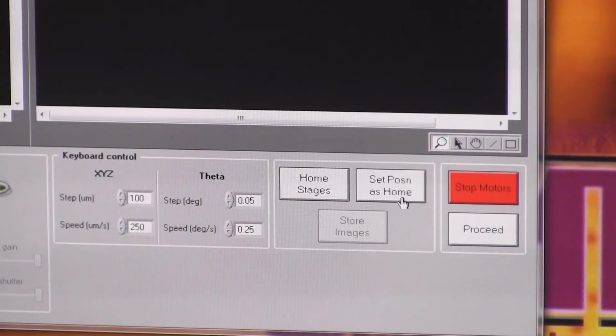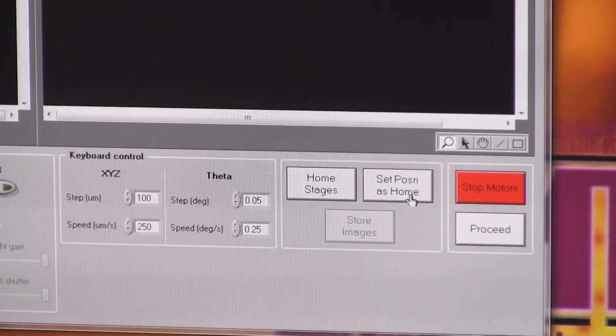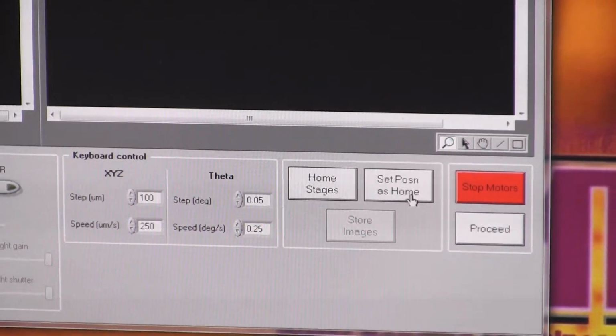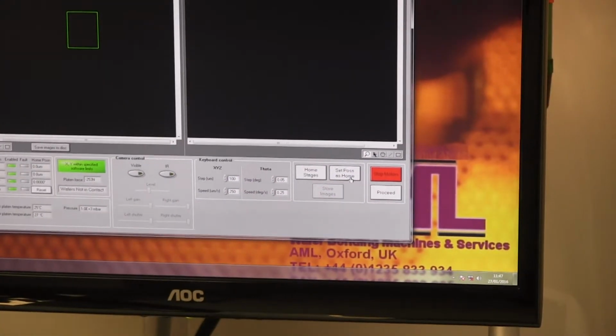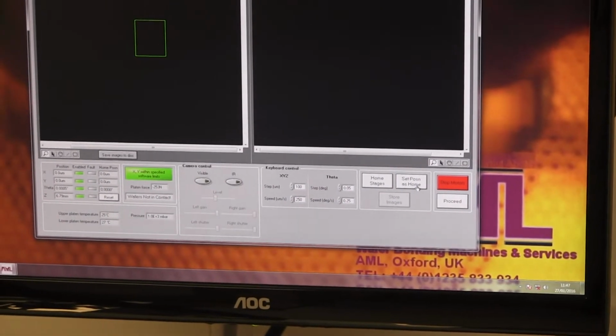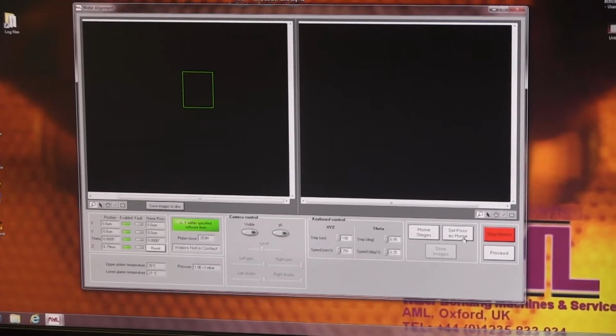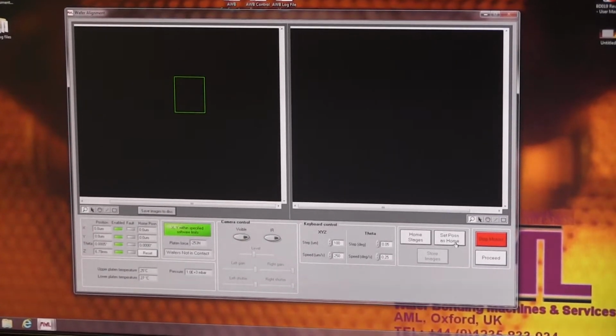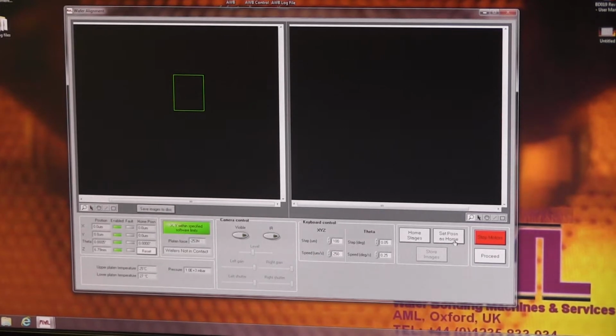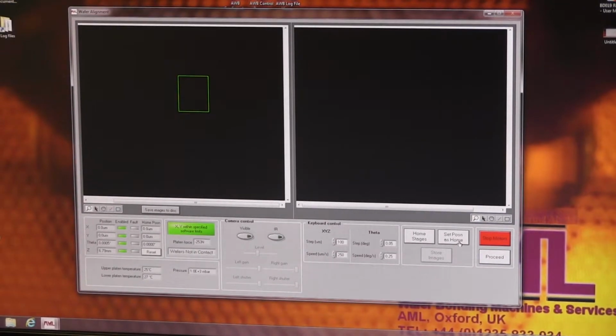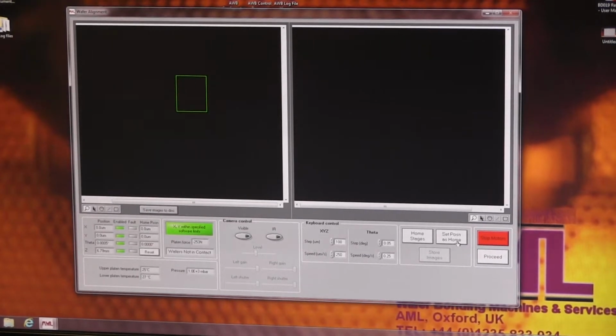At the moment, there's a button here to set the position as home. I've centralized the lower platen and hit that button, and that's set my home position. If I were to offset the manipulator and then set that as the home position, the software limit would then allow me to keep driving further, and then you have the potential to crash the manipulator. So it is possible to fool the software limit by doing that. Please don't — it's there to protect the machine.